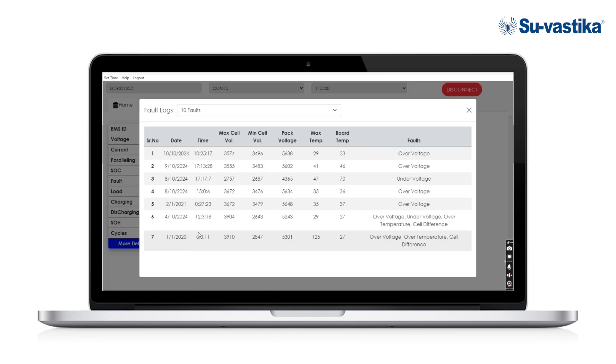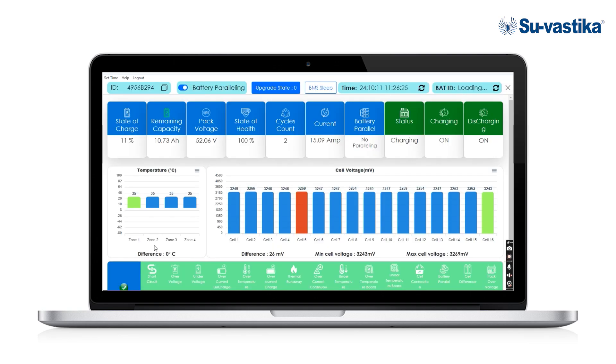These are the fault logs — you can go to the logs and see wherever there was a cell voltage difference. It shows the date and time when there was a difference, and how the BMS has been balancing the cell voltages. This is the main dashboard, showing different temperatures. Since this is a 16-cell battery, you can see the different voltages of each cell, and the BMS is balancing the voltages of each cell, which you can view practically on your laptop or mobile.